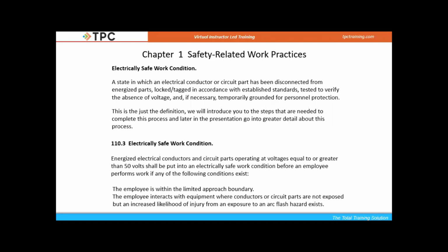And then it comes down into when they really would like to see this electrically safe work condition established. If the voltage of our equipment, and this means any voltage inside of our cabinets, is 50 volts or greater, then our conductors and circuit parts shall be put into this electrically safe work condition, which we're going to look through all 8 steps coming up, before an employee does any work if they are inside the limited approach boundary. So from 50 volts all the way up to 750, that would be if the employee is within 42 inches of that equipment, or the employee interacts with the equipment where those conductors or circuit parts are not exposed.